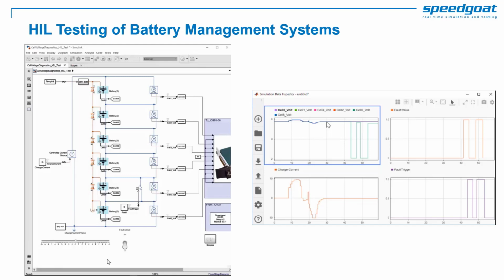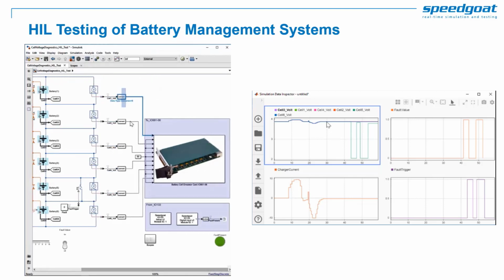One very important aspect for all onboard power systems is energy storage systems, for instance battery packs. You can add battery pack models to simulate battery cells and generate fault scenarios. You can perform diagnostics at the cell level, measuring voltage between cell terminals. In this example, the measured cell voltage values are fed into a driver block for the IO391 module, which converts these numerical values into electrically isolated voltages, each relating to individual battery cells.